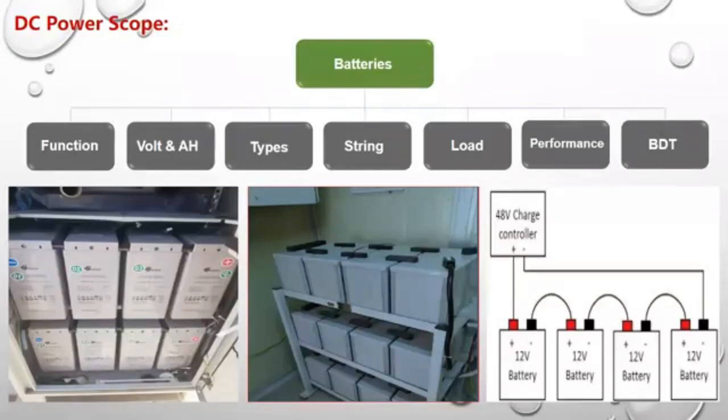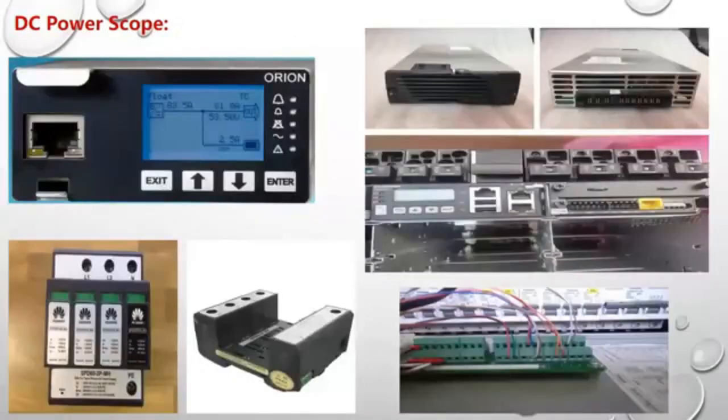Now, last time I told you guys that we'll talk about something that we mentioned later on. We said that for the 12 volt batteries, I connect 4 of them so they give me 48 volt DC, and for 2 volts, I connect 24 so it can give me 48. So let's put that here. Again, if I said 12 volts, then I will need, sorry for that.